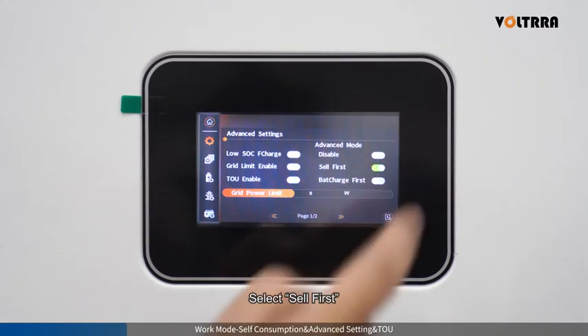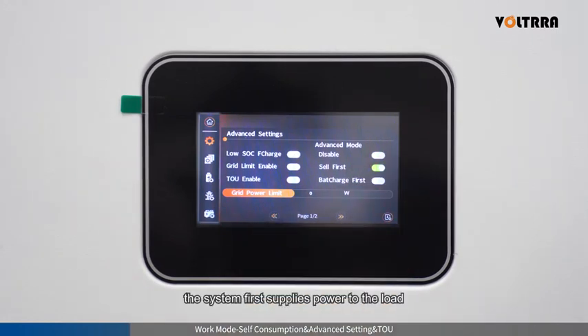Select Sell First. In this mode, the system first supplies power to the load, then exports power to the grid. Only when the grid export power setting is small, and there is still excess PV power after supplying the load and grid, the system will then charge the battery.